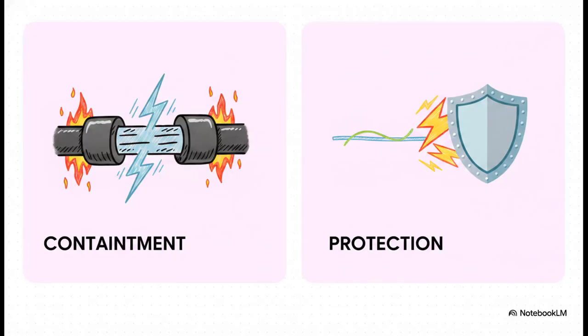Now let's totally shift gears and look at intrinsically safe, or IS, versus non-IS segregation. Notice how the entire protection philosophy flips here. For standard, non-IS heavy power cables, the goal is containment. We are trying to confine the electrical energy inside the equipment to prevent it from igniting the environment. But for IS cables, the logic is inverted. The circuit is already designed to be so low energy that it simply cannot spark.